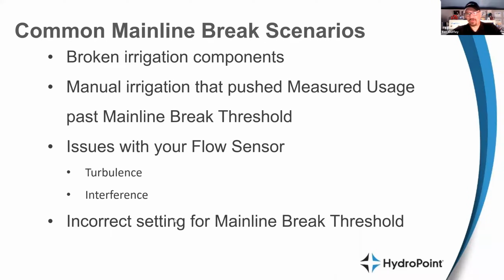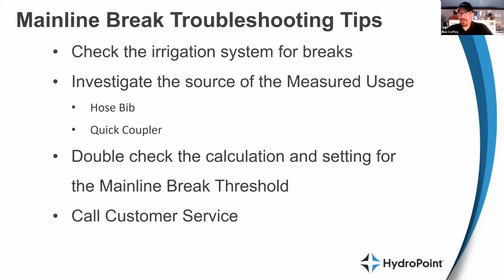Also, electrical interference. If you've got electricity coming across your flow sensor wires, that shows up as extra pulses on the wire and can drive your usage way up. That's why we always use the right kind of wire, and obey the rules of electrical installation for those flow sensors. And then last but not least, of course, could be an incorrect setting. If we didn't set that mainline break alert to the right threshold, that's something we want to keep an eye on. So when we are troubleshooting, like Eric said, you start at the beginning and walk through.